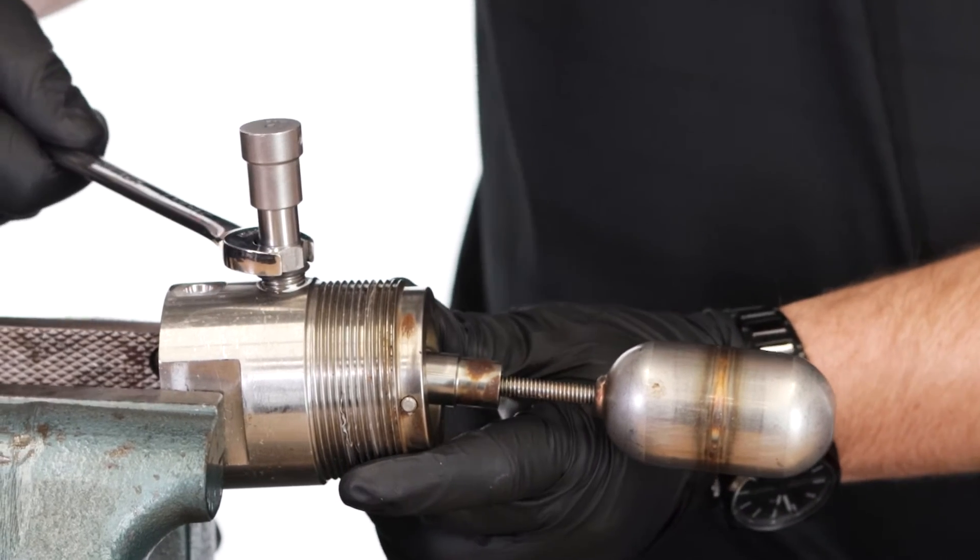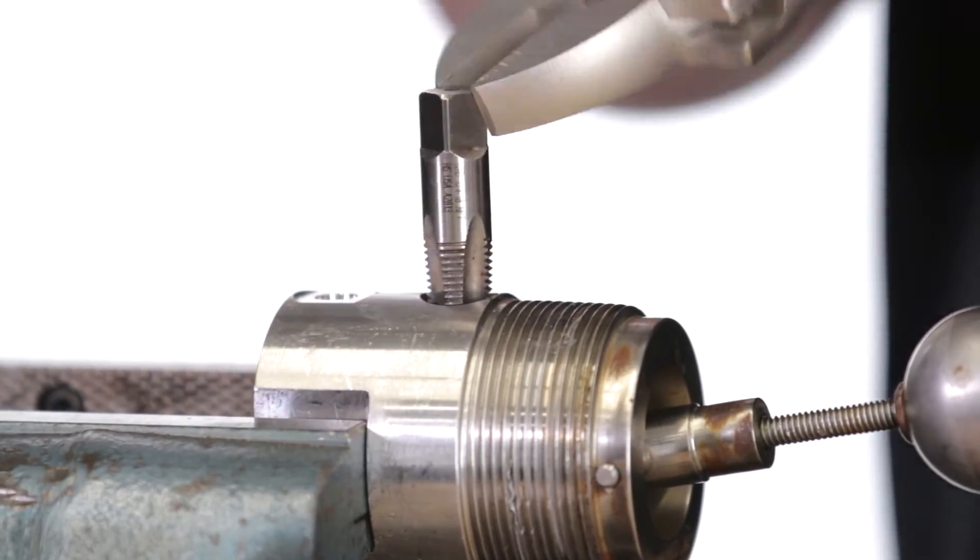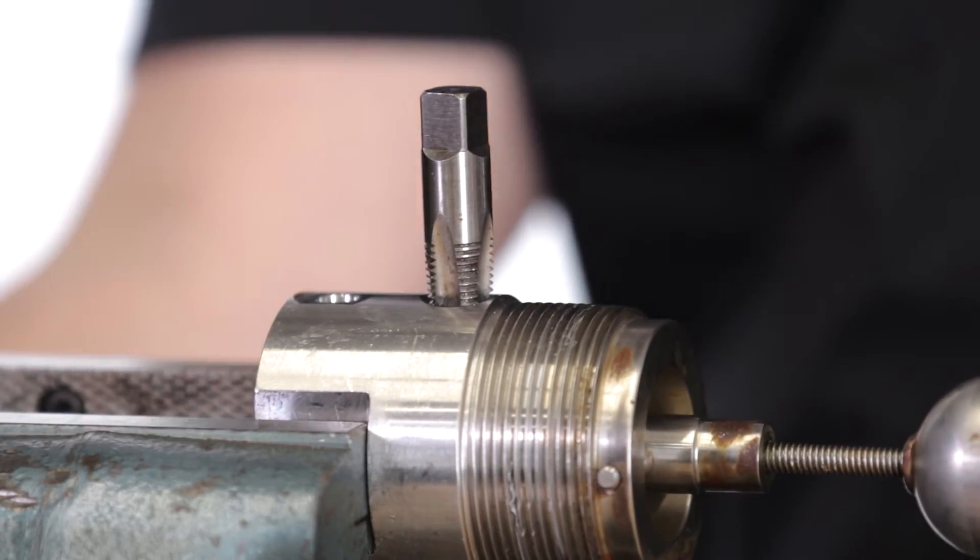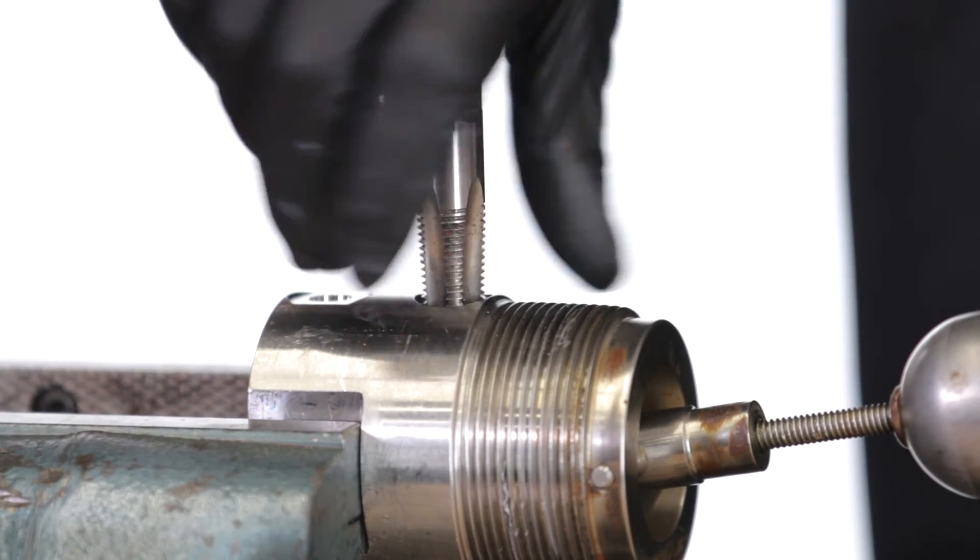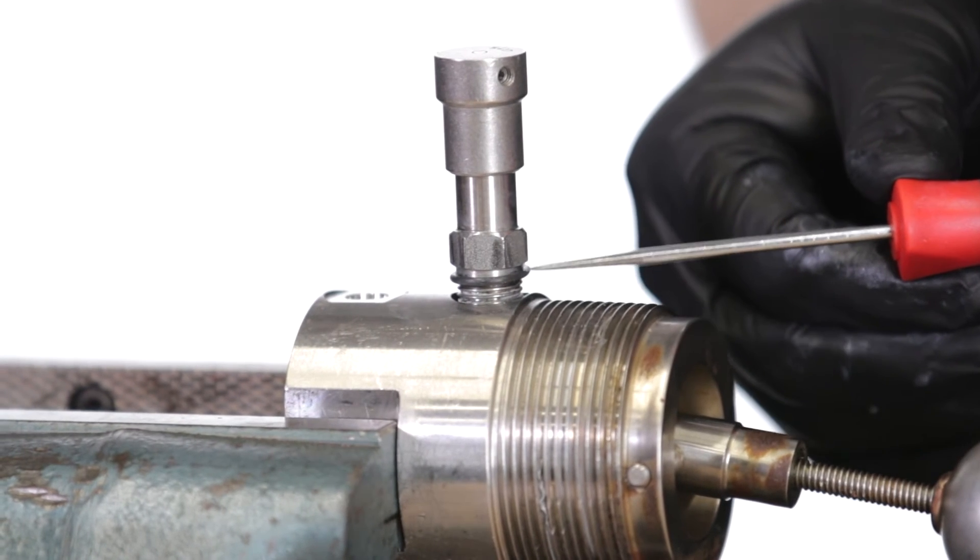On this old level switch, we found the internal threads were messed up and were unable to thread the fitting back into the body. After trying a quarter inch tap with no success, at this point we would need a new level switch because a replacement body would not be cost effective. For the purpose of this video, we'll leave it partially unthreaded and continue showing the repair process.